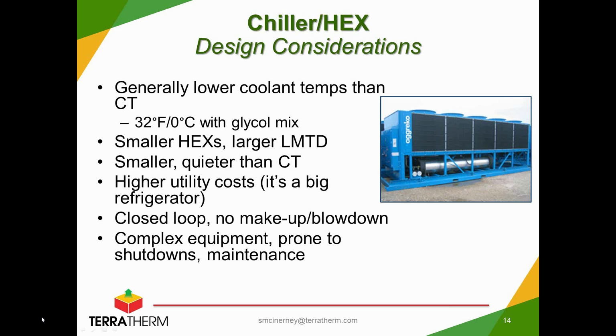On the flip side, with chillers, you pretty much can dial in the operating temperature you're looking for, down to or even below the freezing point of water with a glycol mix. And so with the cooler temperatures that you can expect from a chiller, you can use much smaller heat exchangers because of the larger driving force between the process and the coolant fluid. The packages themselves can tend to be smaller and quieter than a cooling tower.